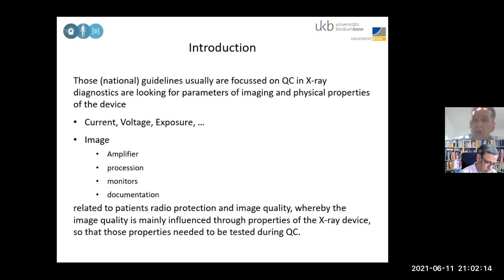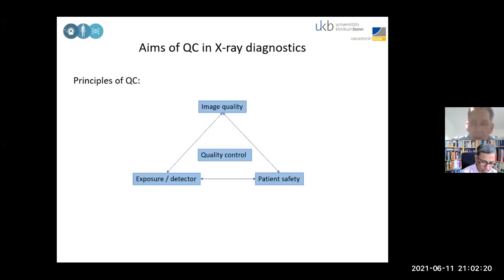So you see there are several steps you have to follow in this process. This triangle actually shows what I already said in the introduction: image quality, exposure and the detector, so the X-ray device, and patient safety are the most influencing parameters to be checked to have a good quality control in X-ray diagnostics.